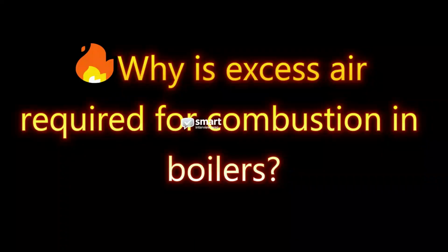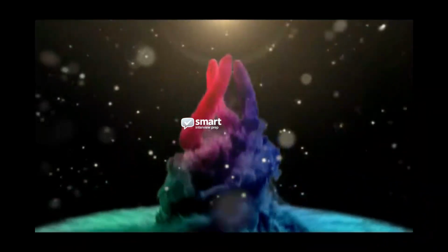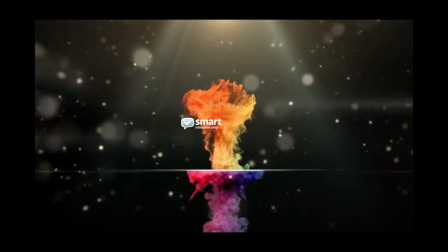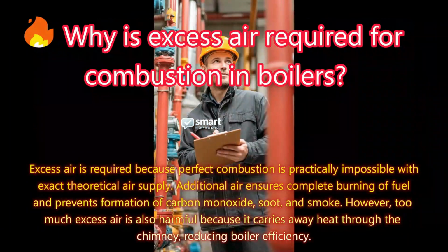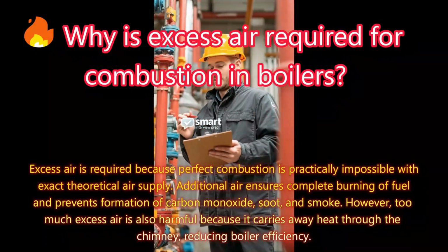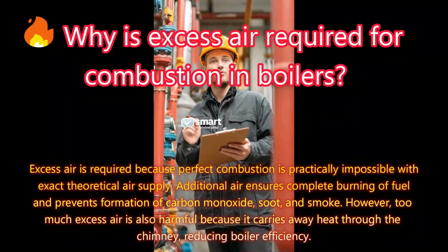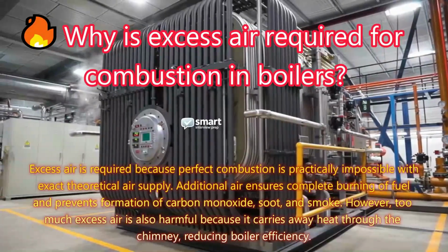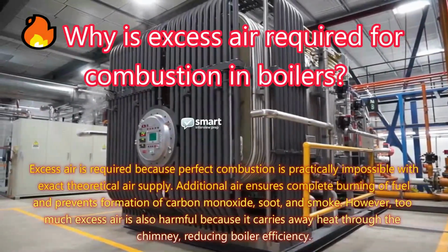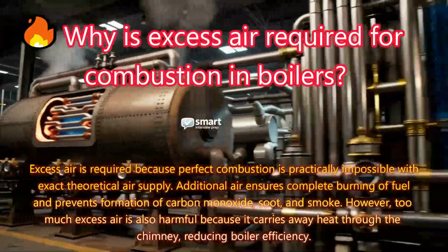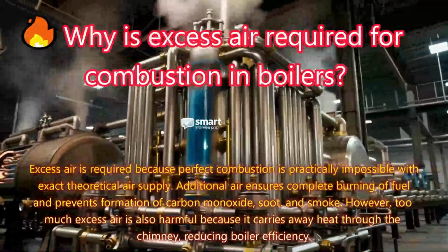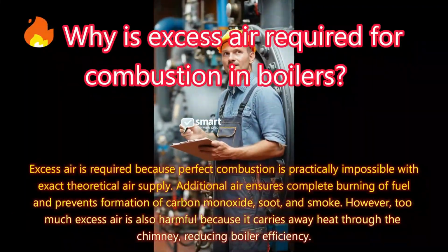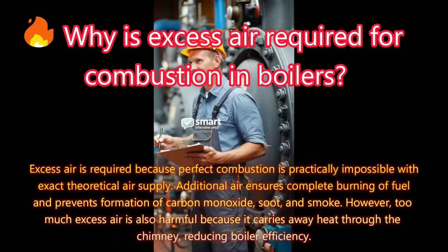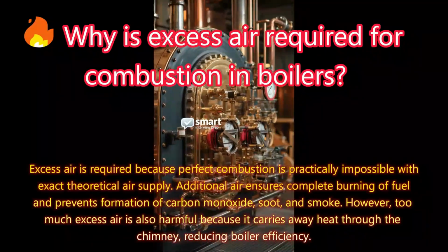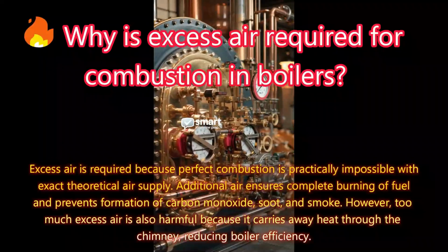Why is excess air required for combustion in boilers? Answer: excess air is required because perfect combustion is practically impossible with exact theoretical air supply. Additional air ensures complete burning of fuel and prevents formation of carbon monoxide, soot, and smoke. However, too much excess air is also harmful because it carries away heat through the chimney, reducing boiler efficiency.